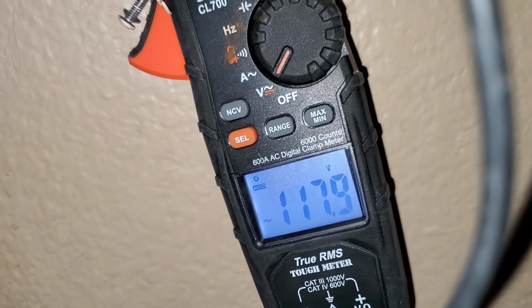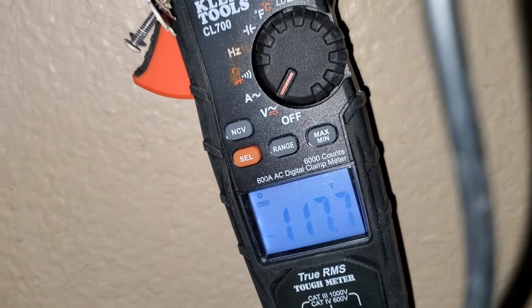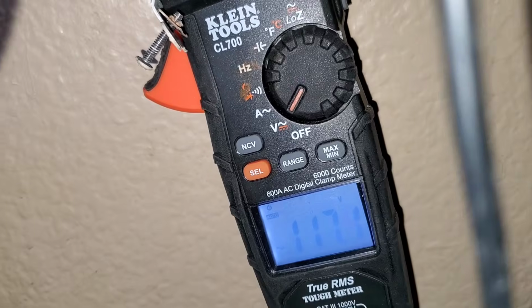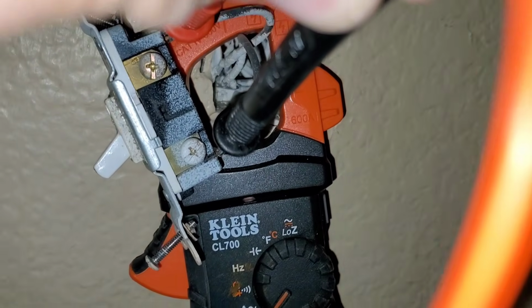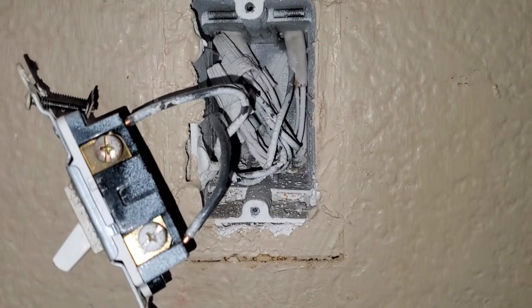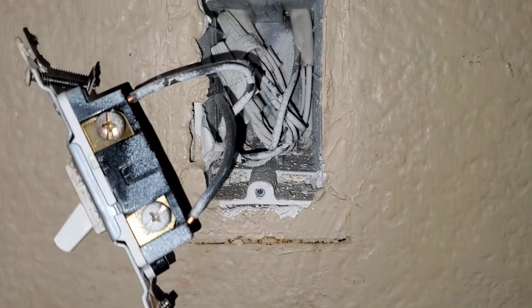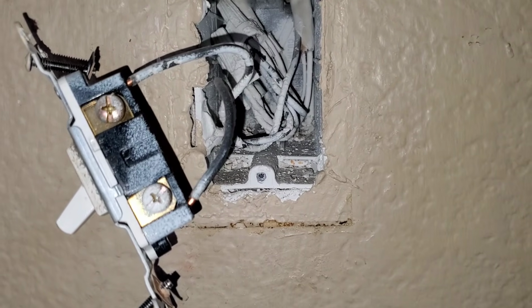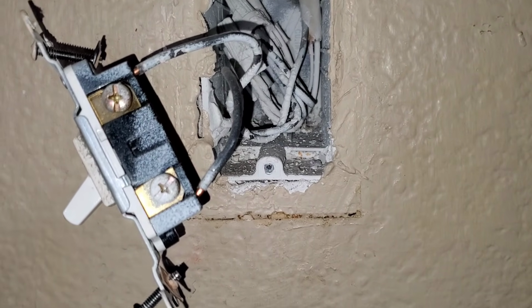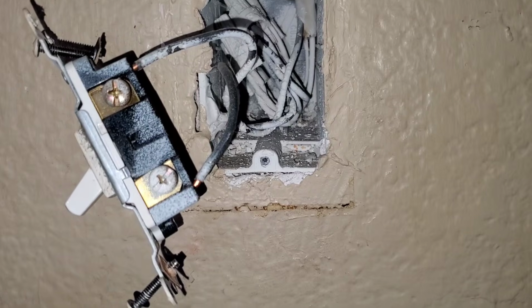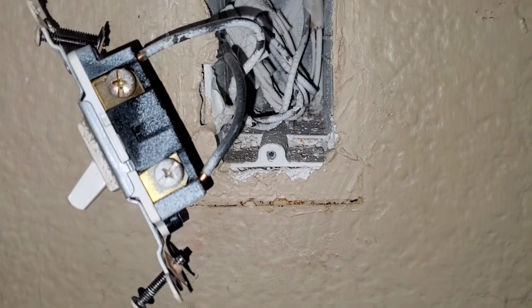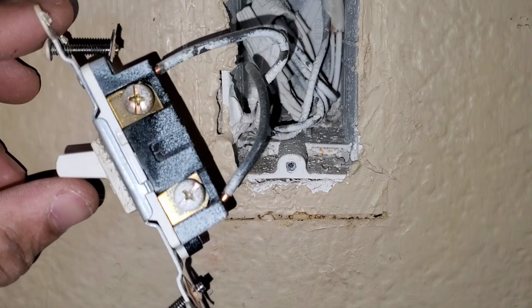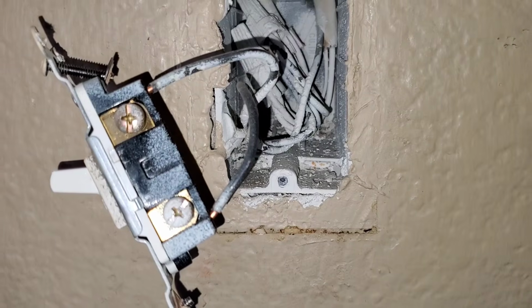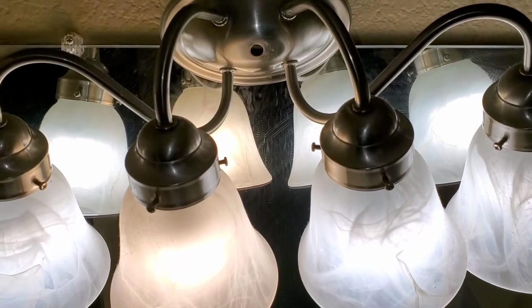This is important to understand: I have 120 volts coming into the switch, even though the switch is in the off position. Now I'm going to turn the switch on. A lot of times when you mess with these switches and move them around, it'll fix whatever the issue was with sending voltage to the light fixture. You can see I turned the switch on and now my lights are working.